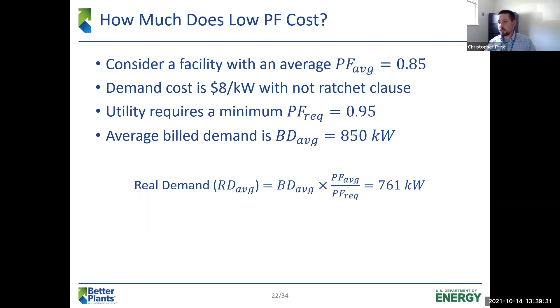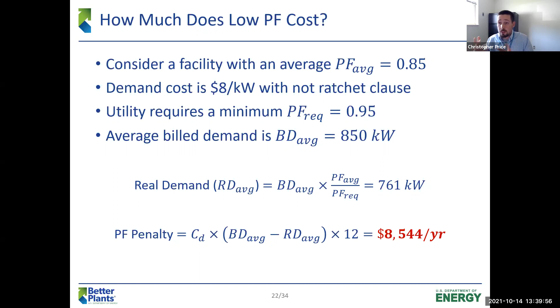Figuring out what the real demand is, you would use that first formula I showed you, except flip it because we're going to find real demand, not the adjusted demand. When you work through it, what you'll see here is that every month, the bill is adjusted upwards by about 90 kilowatts because the power factor is below the requirement. If you multiply that 90 kilowatts by the $8 a kilowatt, over the course of a year, you're talking about $8,500 or more in penalties because the power factor is too low. This just gets worse if your power factor is 0.8 or 0.75. And you may not know that that penalty is there because it's not a separate line item on your bill.